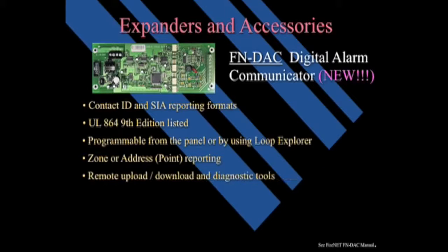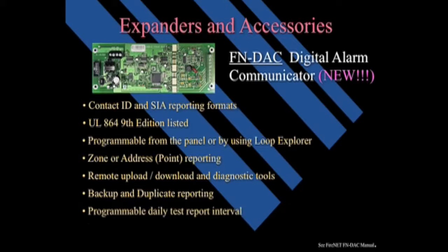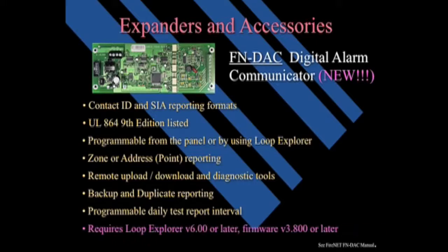The FN-DAC supports remote upload, download, and diagnostic tools through a dial-up connection. Provides backup and duplicate reporting. It has programmable daily test report intervals. The FN-DAC requires Loop Explorer version 6.0 or later and a firmware of 3.800 or later.